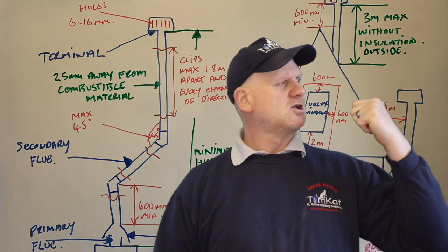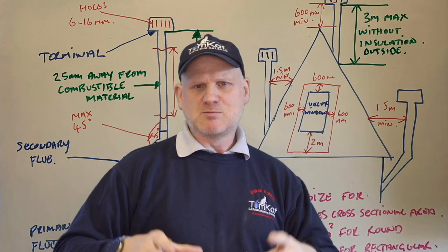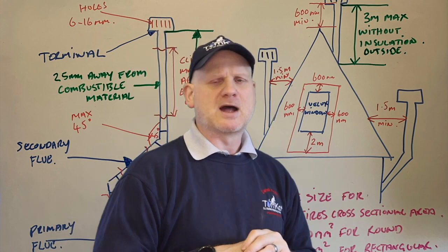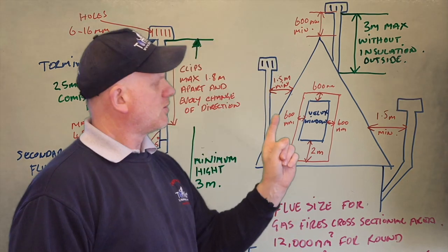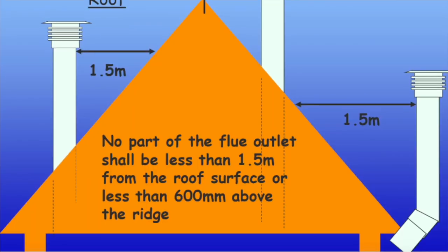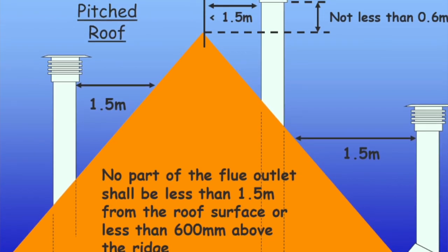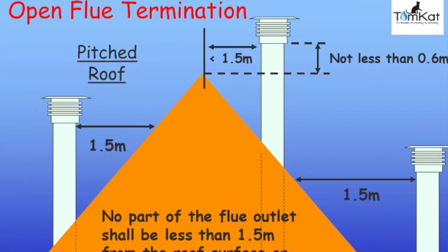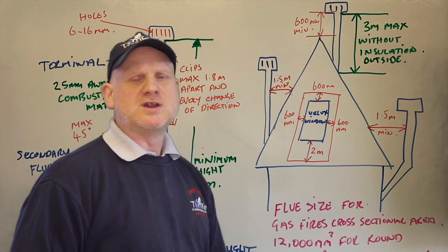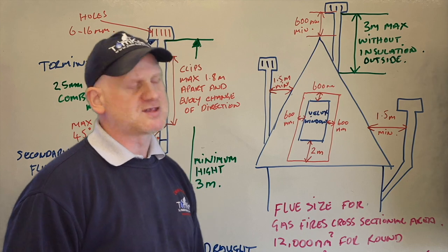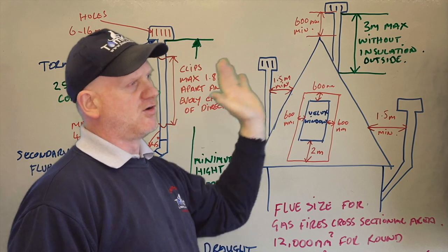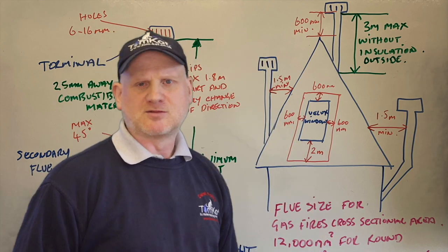When exiting the building, let's look at the positioning of the flue off the pitch of the roof. From the side of the flue to the roof on a horizontal plane, you need more than 1.5 metres away. At the top, we need to go above the ridge more than 600mm. Those are the major things to look out for when open flued appliances are exiting through the roof.